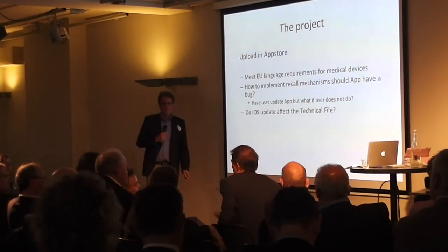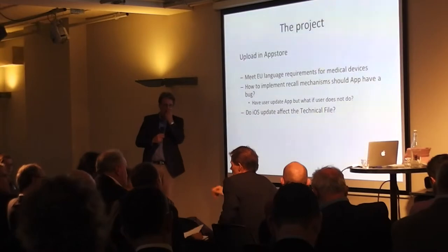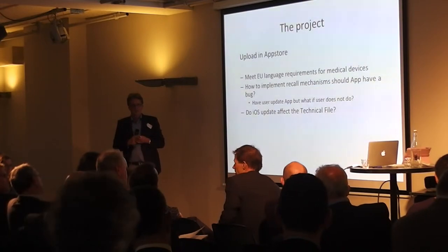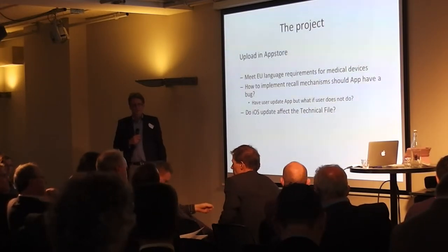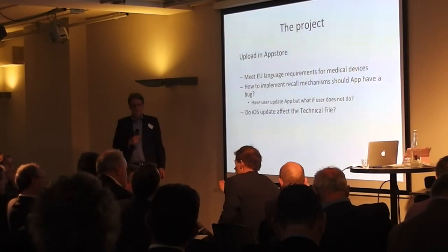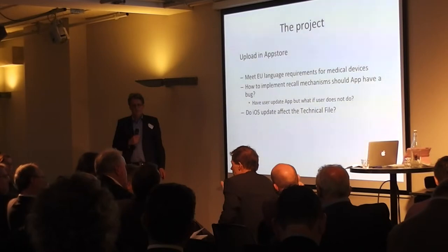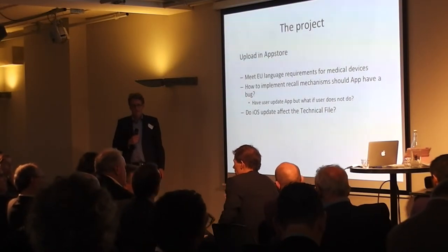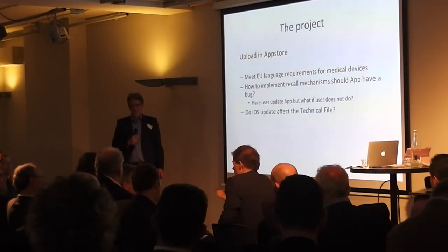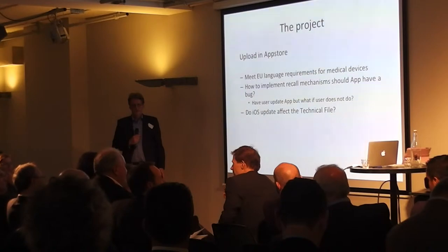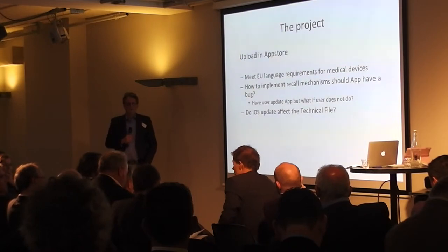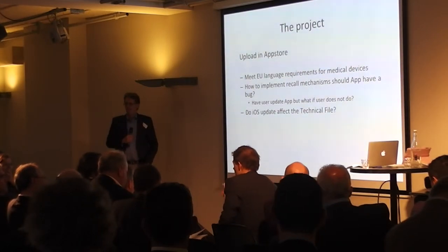So under the new medical devices regulation, there's a supply chain regime that's put in place, and that actually also addresses specifically distributors in the definition that we also put in a distribution platform. So Apple would be an importer or a distributor or both under the new medical devices regulation when that enters into force. Then they also have their own autonomous obligation to have a process in place to verify compliance of the manufacturer. So then they are going to be obliged to verify that the manufacturer has done the required conformity assessment, for example. So this is going to be a lot of work for them.